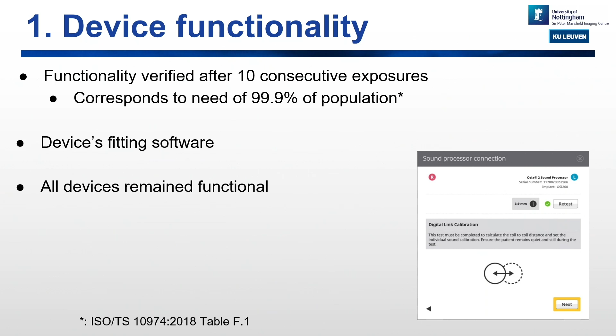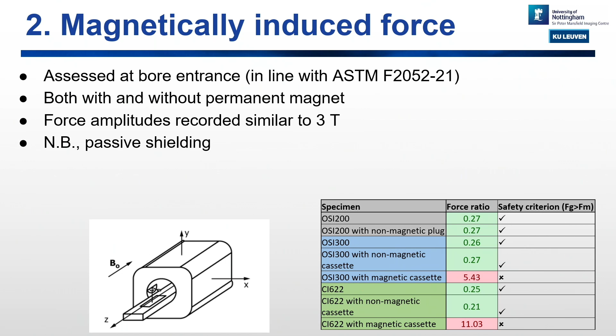For magnetically induced force, the device was suspended on a string and positioned close to the bore entrance where the spatial gradient field is at its highest. We then deflected the device by adding a known mass of something like plasticine or Play-Doh and measured the angular deflection to derive the magnetically induced force. Force amplitudes were found to be similar to those seen at 3T, and all of those with the retaining magnet removed were trivial. We here show the ratio of the gravitational force with the magnetic force.